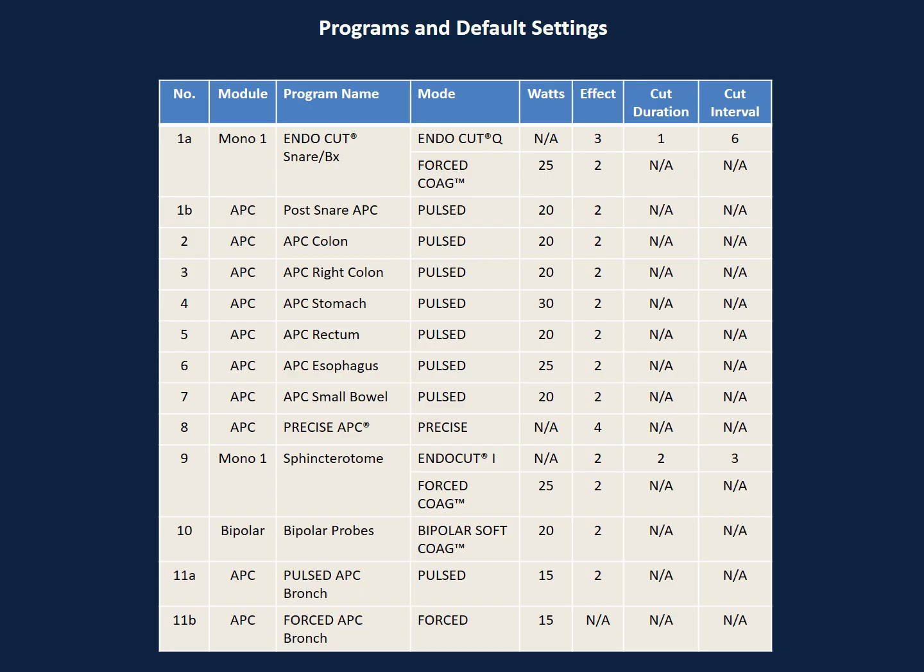The modes vary between electrosurgical units, and the terminology is specific to the manufacturer. The ERBE unit offers several options between two currents: cut and coagulation. They differ primarily in the rate and magnitude with which they induce a temperature increase within the target tissue. Coagulation currents induce a slower increase in temperature within the cells, between 70 and 100 degrees Celsius, causing them to dehydrate and shrink without bursting. Cut current causes more rapid heat increases to temperatures above 100 degrees Celsius, causing the cellular water to boil and the cell to rupture, leading to cleavage of the tissue along the active electrode.